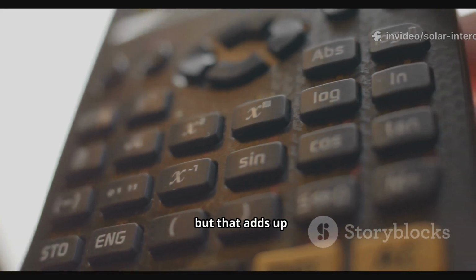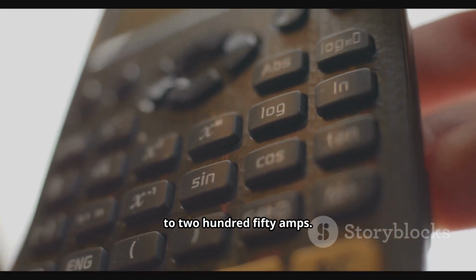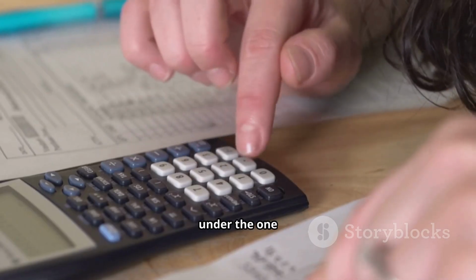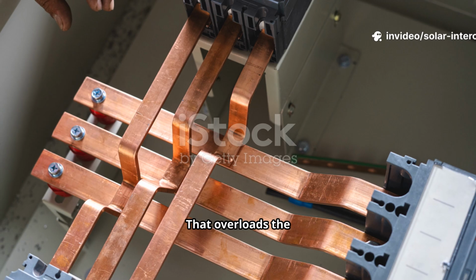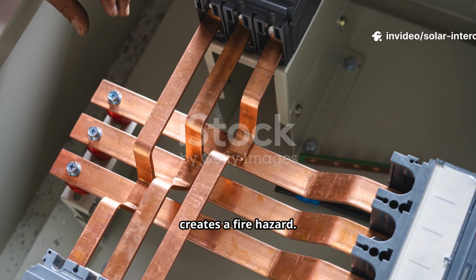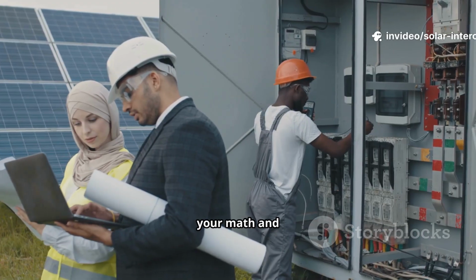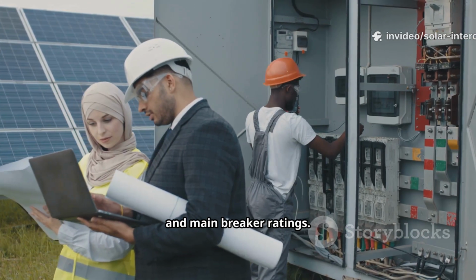Thinking it's okay. But that adds up to 250 amps. The limit is 240 amps under the 120% rule. That overloads the panel busbar and creates a fire hazard. Always double-check your math and confirm panel busbar and main breaker ratings.